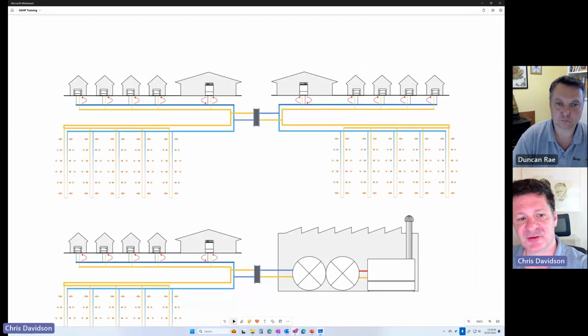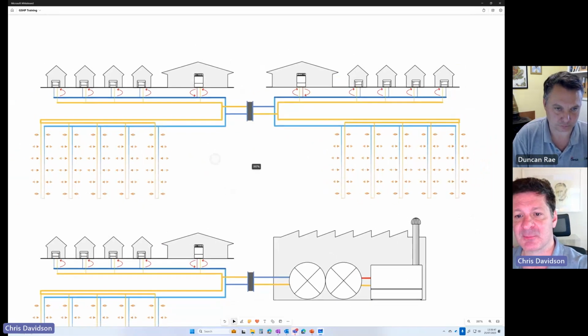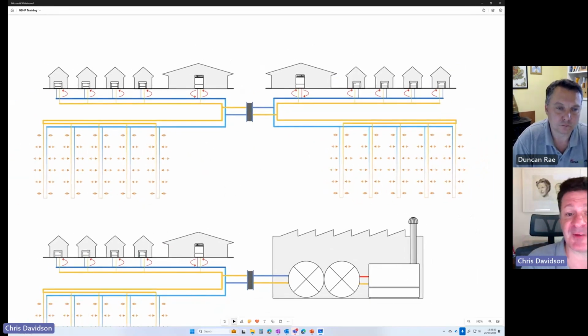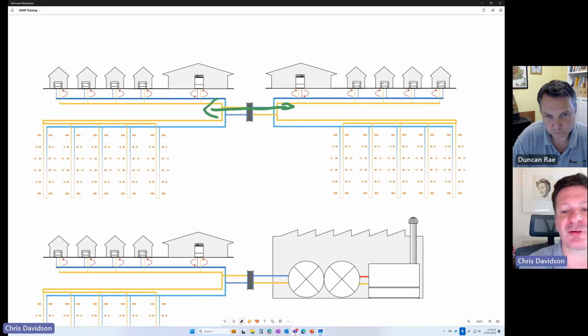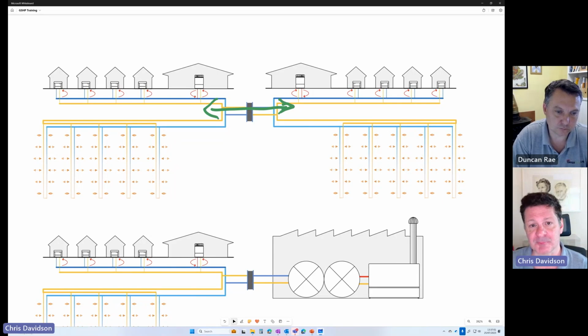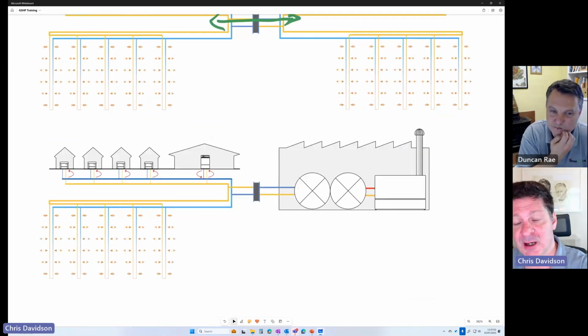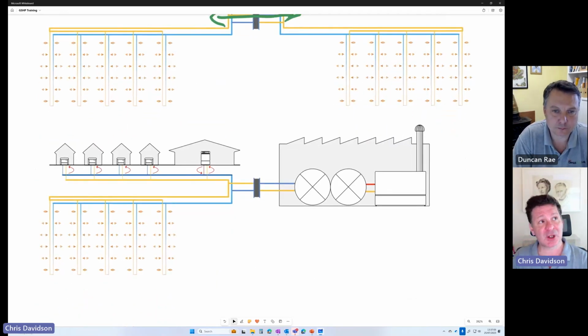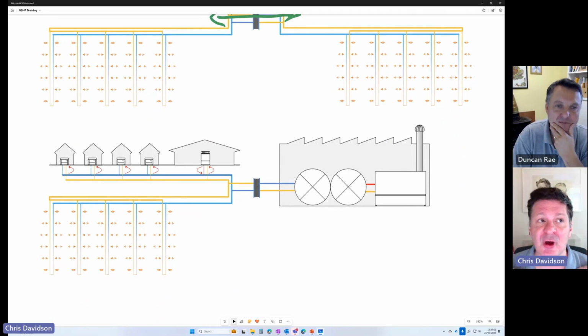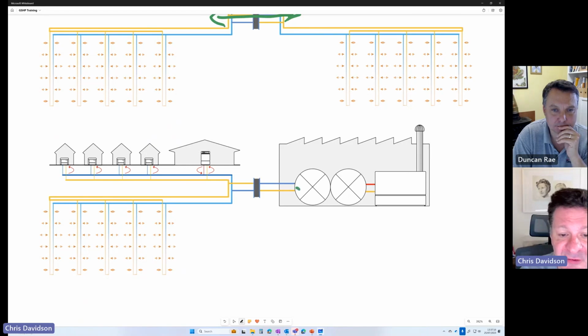Now, back to your question a second ago, Duncan, about heat networks and how they can be connected together. We can connect various ambient heat networks together, and because of the diversity and the differences in the loads between those networks, we are naturally going to get energy flowing to and from, which will make both networks more efficient. We could also connect this to an older generation heat network. One common problem in 3rd and 4th generation heat networks is the return temperatures coming back higher than they're designed to be. So we can take some of that heat and put it into our heat network.